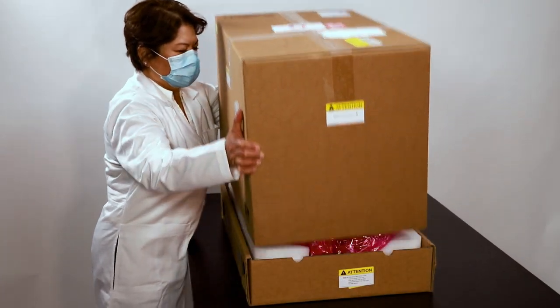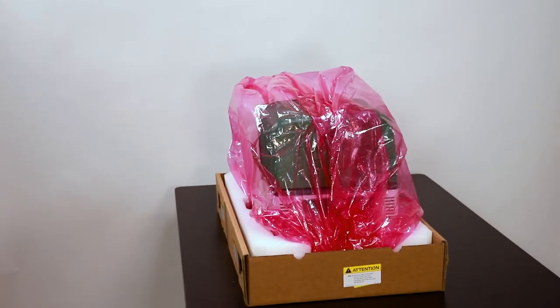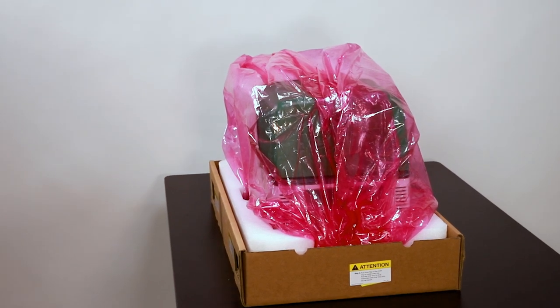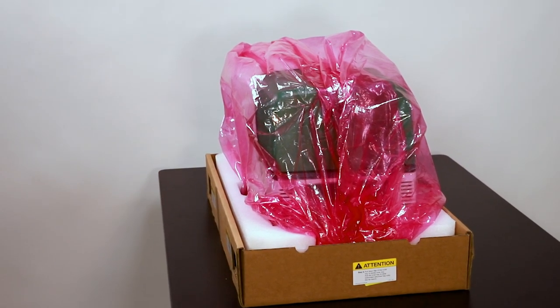Lift the top of the box, leaving the instrument sitting on the cardboard base. If any protective foam remains on top of the instrument, remove it.